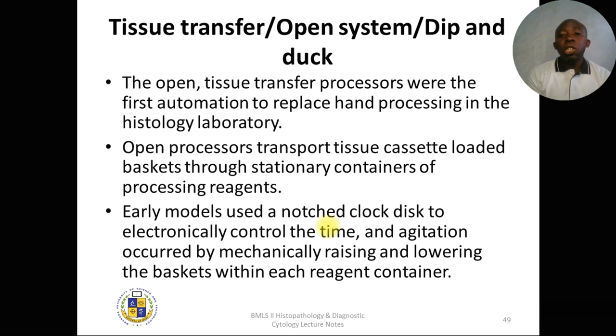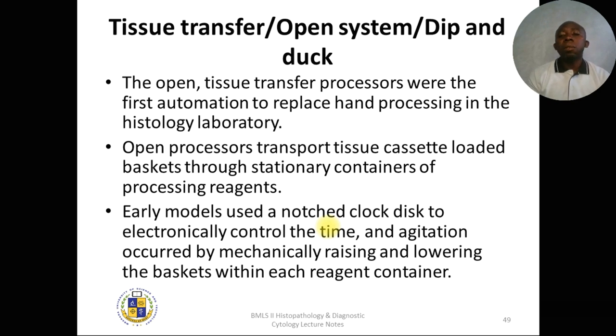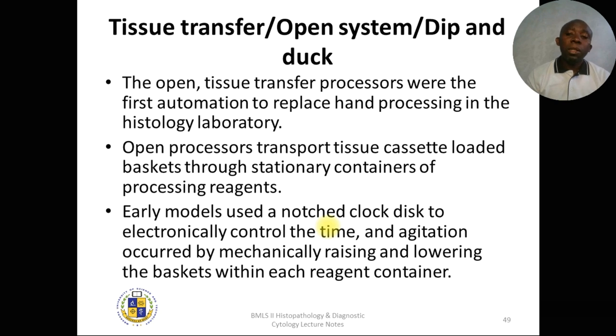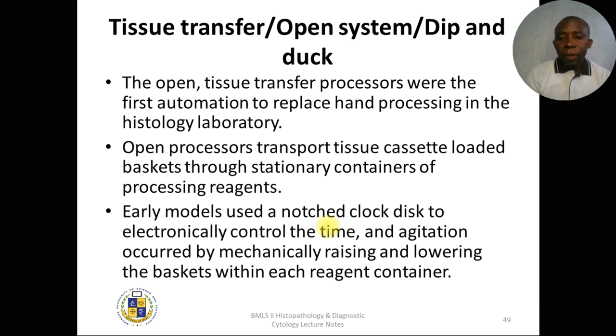Open processors transport tissue cassettes loaded in a basket through stationary containers holding the processing reagents. The cassettes are placed in baskets after grossing, and taken to the machine for processing. The containers are stationary — it is the tissue that moves into the respective containers. Early models used a notched clock disc to electronically control time, and agitation occurred by mechanically raising and lowering the basket within each reagent container.